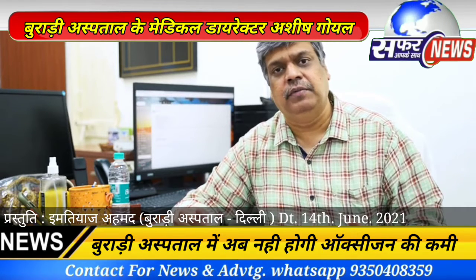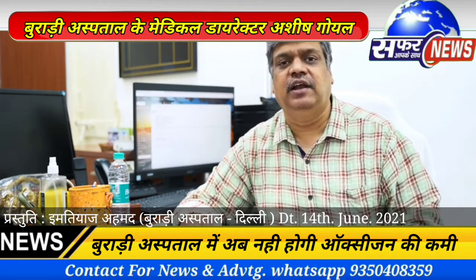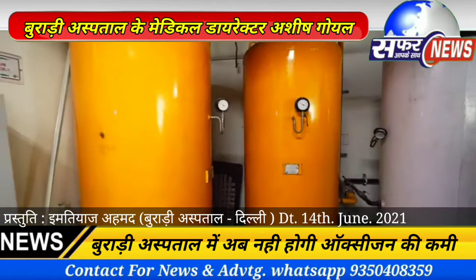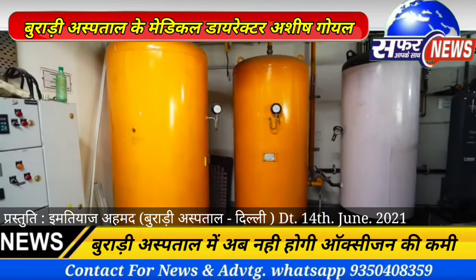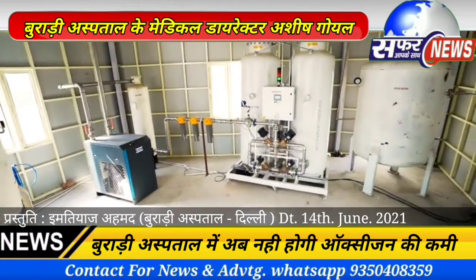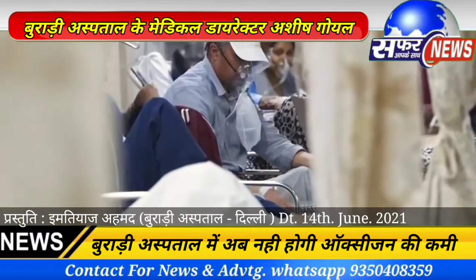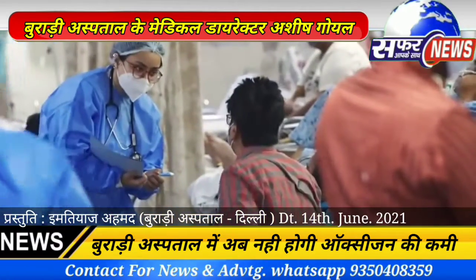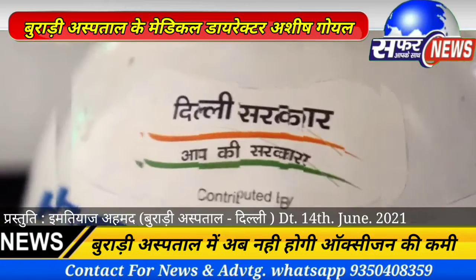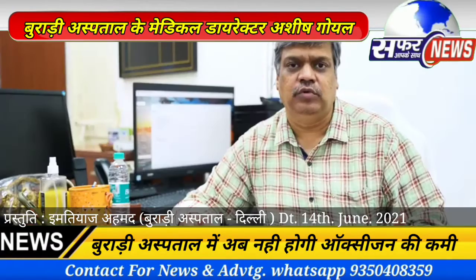The 500 liters per minute plant gives us the equivalent of about 100 cylinders of oxygen. So our total oxygen generation is about 300 to 350 cylinders. With this capacity, we can treat 200 to 300 patients without any external support. In addition, oxygen cylinders are available here — we have also been given 1,000 cylinders, which we also use.